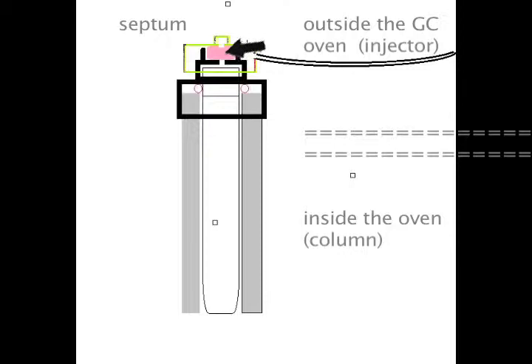So the needle goes through the top nut, through the septum, through the bottom nut. The whole system is pressurized from the top and sealed with the o-ring. To take it apart, it's fairly simple. The top nut, which is green, is unscrewed, revealing the septum. The septum is then pried out, and this loosens up the lower nut, which is black in this drawing. Then that unscrews. When that nut is taken off, the port liner is just sitting there and the o-ring is just sitting there. Just pull them both out. Put the new port liner in, slide the o-ring over it, slide the black nut over that, snug it down. Put the new septum in, put the green nut back on, and snug it down. That's pretty much all there is to it.